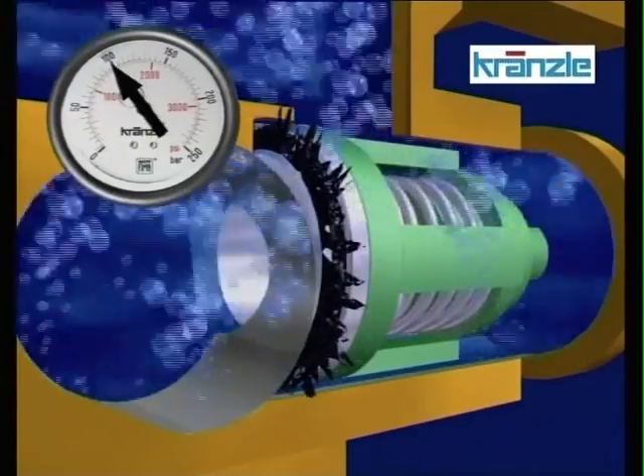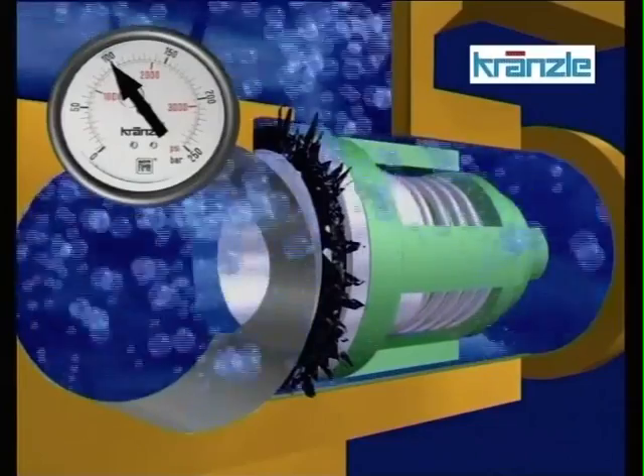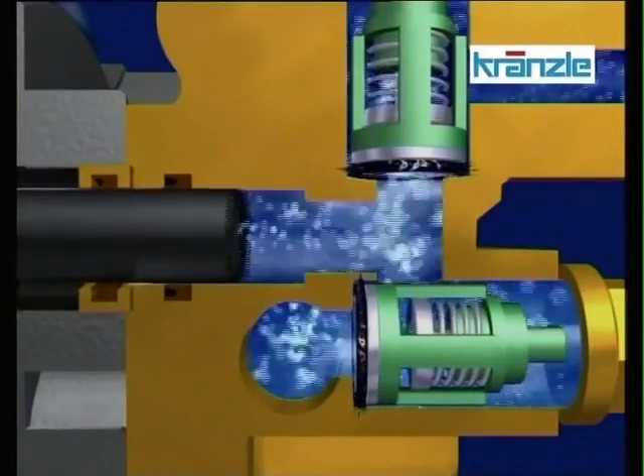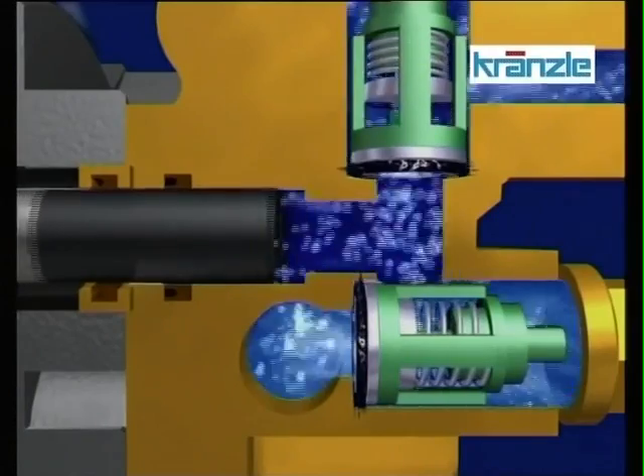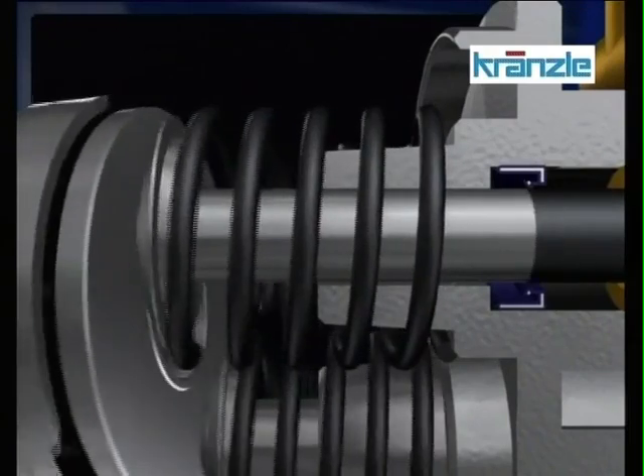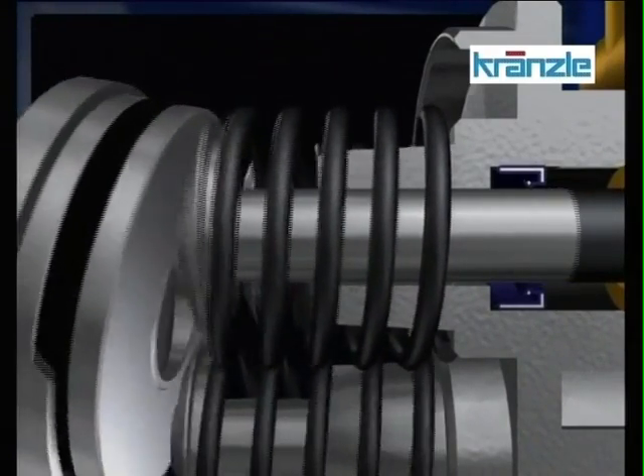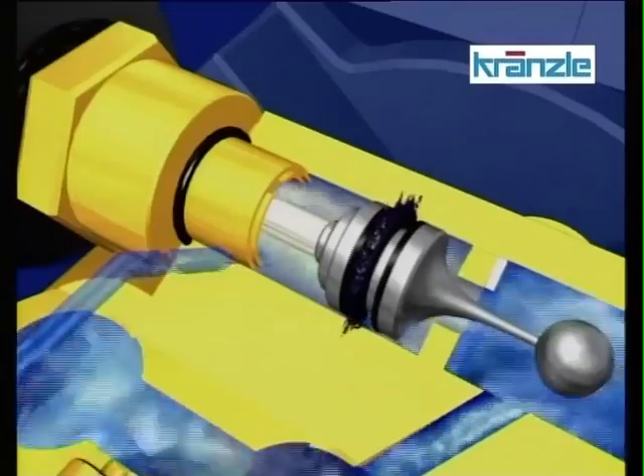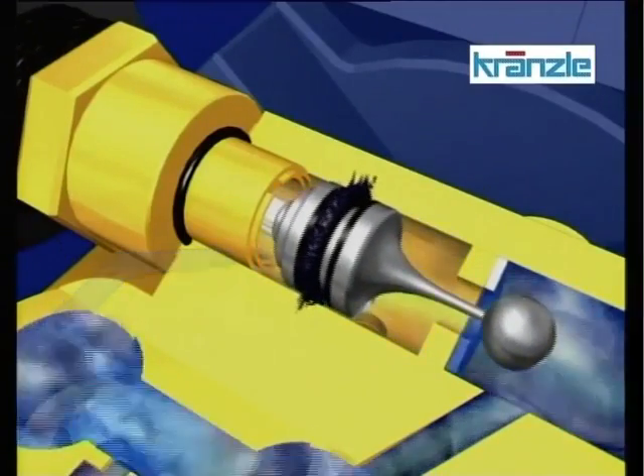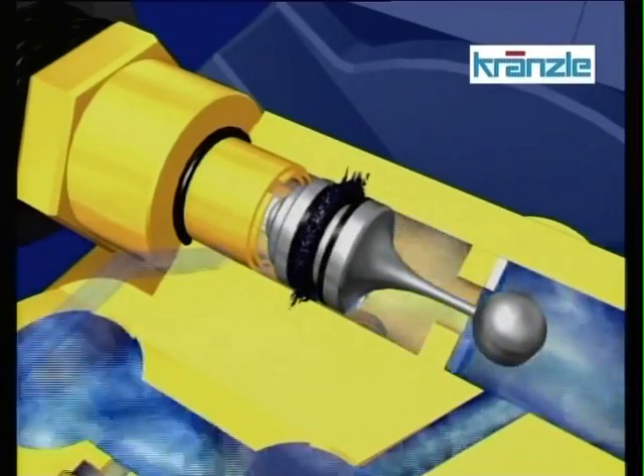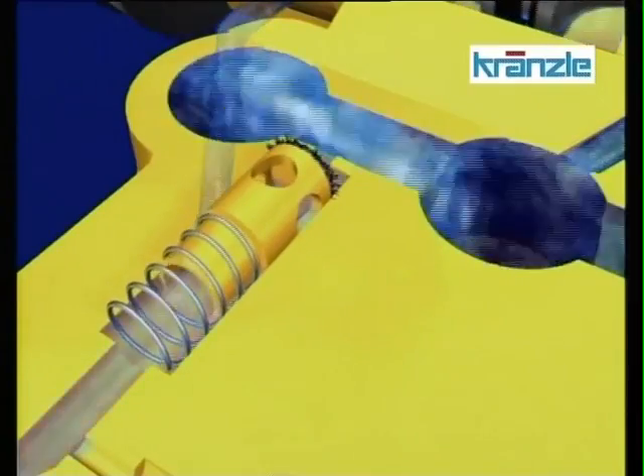This mixture of air and gas is compressed, causing the high-pressure cleaner to function improperly. Seals and gaskets are destroyed. Therefore, make sure to use water with temperatures not exceeding 60 or 70 degrees Celsius, according to equipment, and an admission pressure of approximately 2 bar. Insufficient water may also cause control piston and check valve body seals to be damaged.